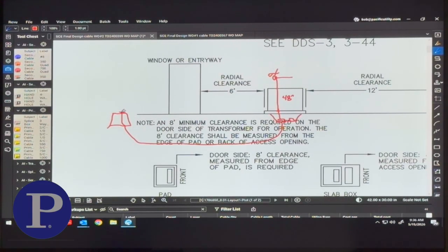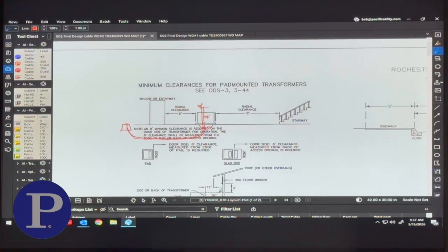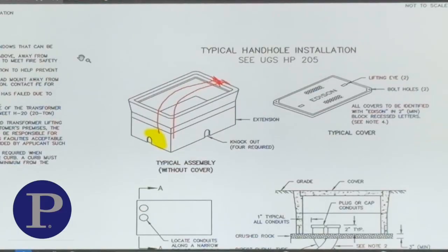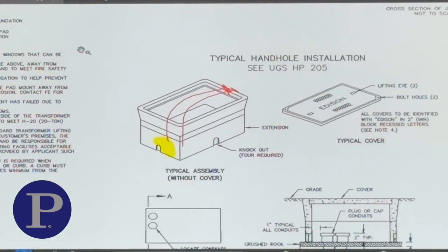If you're going the other direction, you're going to pull it in, pull it roughly 48 inches above the pad, and then again, you're going to cut it at the other end of the handhole from the duct side. Now, just to reiterate, when you're pulling up on this side or feeding in on this side, you want to cut the cable to the opposite side of the handhole from where the duct sits.